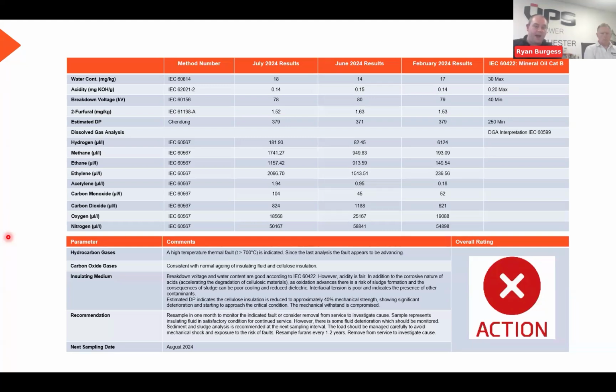So this particular asset had a high temperature thermal fault, which is quite hard to see maybe on the screen, but as you can see over time, the ethylene in February 2024 was still high at 240. So that then triggered our customer to resample it in June. And in that time, you can see that it's taken a significant jump from the 200 to the 1500. So then they resampled again in July, a month later, and it had gone up again.